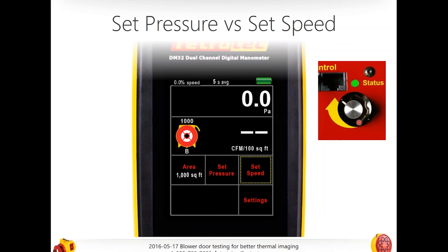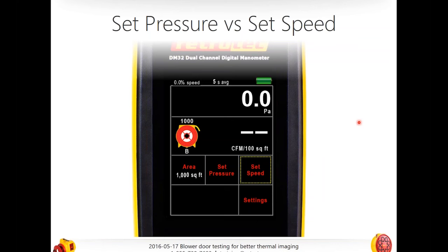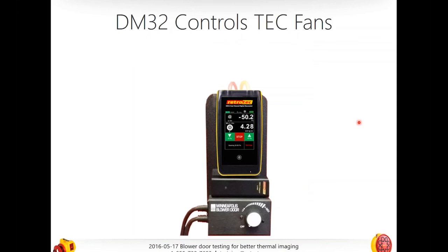You might even want to use the manual knob if you're doing a lot of testing and haven't had a chance to charge your gauge. You don't really need the gauge running to use an IR camera — you just need a pressure difference, and you can use the knob on the side. The reason to use set speed: when you don't care about the specific pressure, when you're not looking for specific quantitative results, but just want to depressurize a building to achieve certain effects — in this case, for infrared camera imaging.